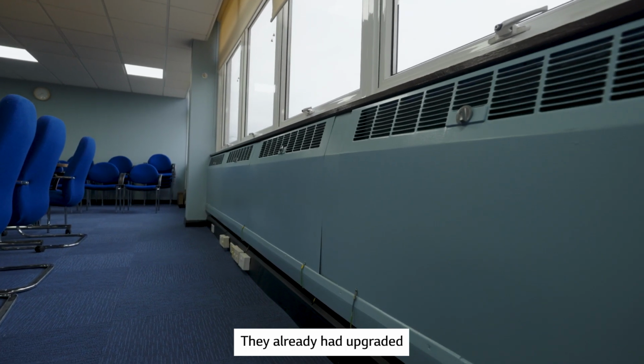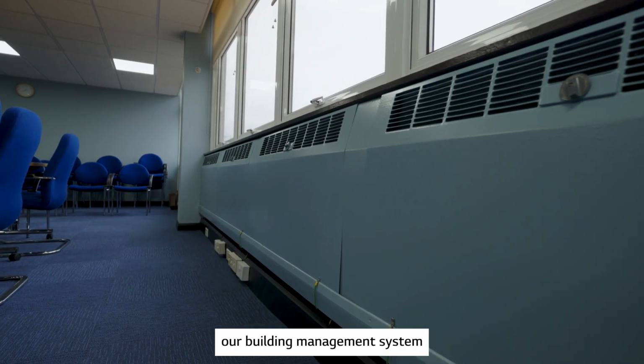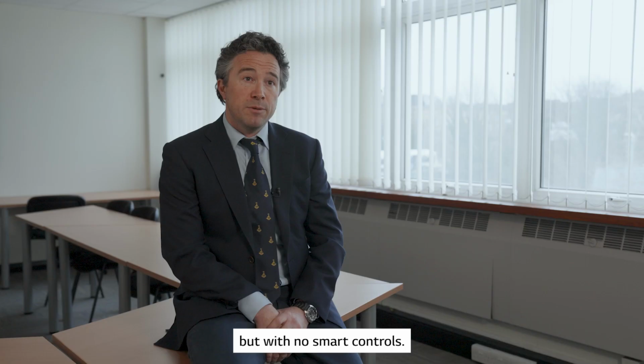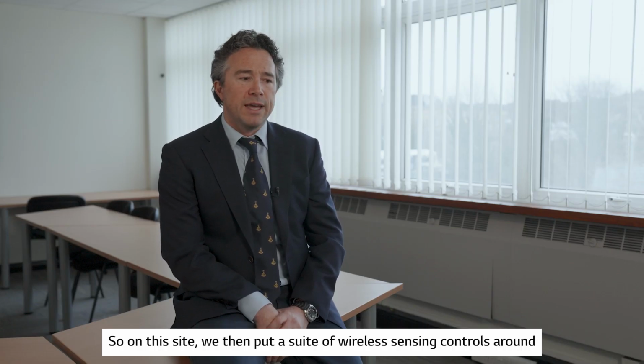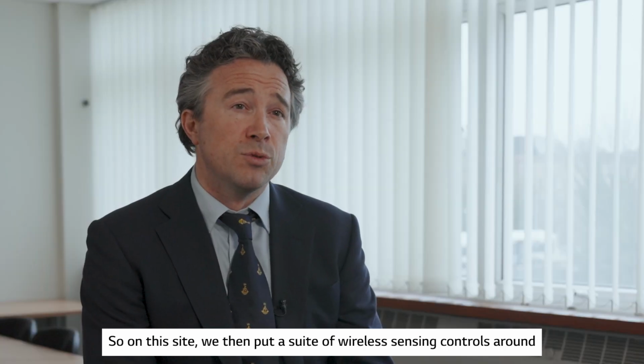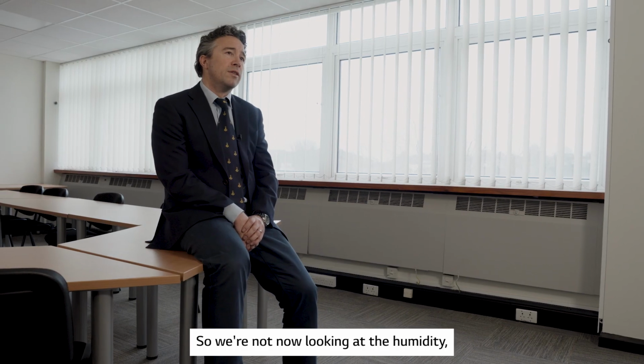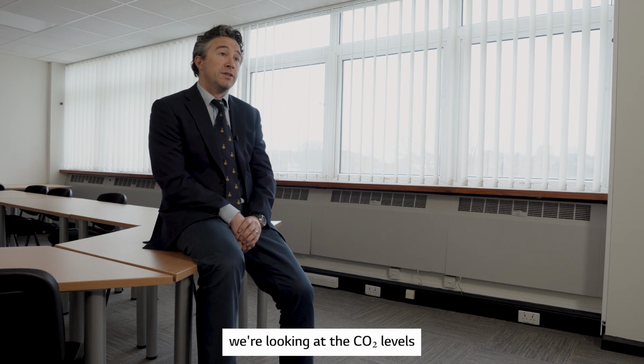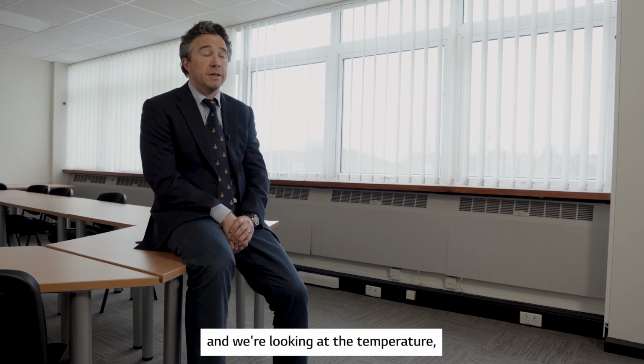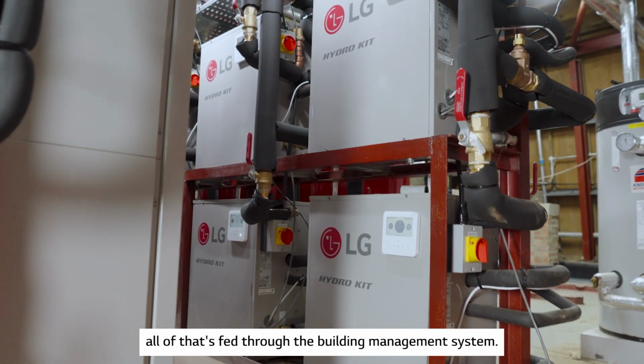They had already upgraded their building management system to run the existing gas boilers, but with no smart controls. So on this site we put in a suite of wireless sensing controls. We're not now looking at humidity, we're looking at CO2 levels, and temperature, all fed through the building management system.